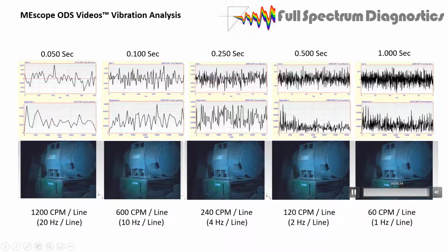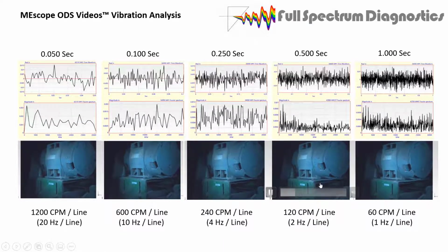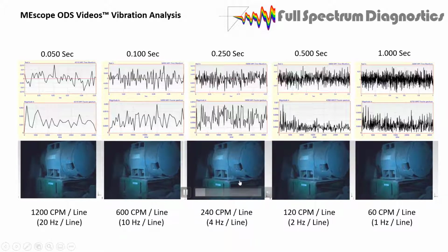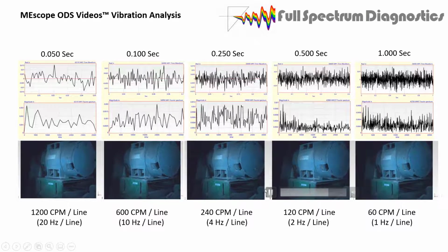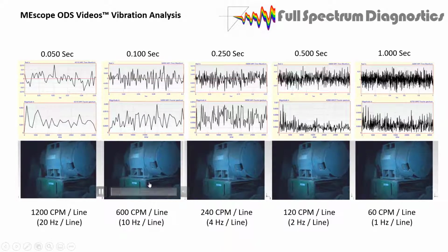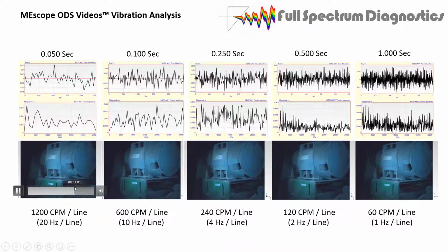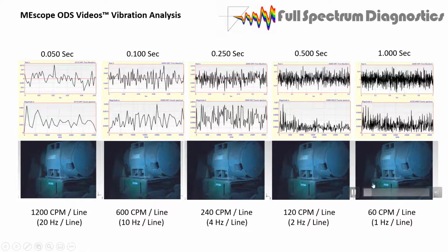1 second of data, I'm getting a clean spectrum and clean animation. What's different about this one is it looks a little blocky, a little choppy. These don't have deformation in the deck the way this one does. So this one, you can see the deformation. This one, the deck's flat. It doesn't look like it's distorting. This one's getting to the point where it is distorting.